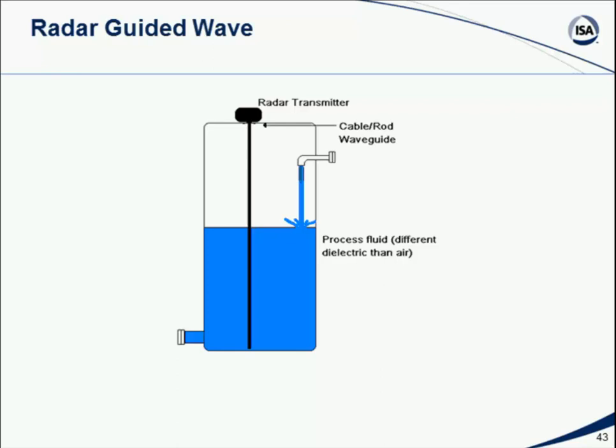Well, with guided radar, when we send the pulse down the guide, generally it's going to be reflected back by the first interface it sees, so the process fluid level. But in many cases, enough of that radar energy will continue down the guide to where it will either hit the bottom of the tank, so we'll have a bottom measurement, or if we have another liquid down there, let's say there's water at the bottom of this tank or something else, when it hits the interface between the blue fluid and whatever's at the bottom of the tank, we'll get another reflection. So quite often with guided radar systems, we can actually not just determine the level of the primary fluid in the tank, but we can also detect the bottom.